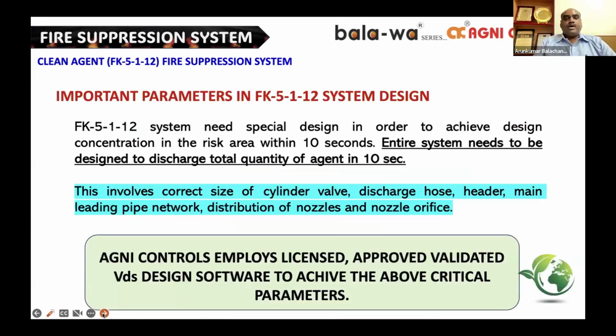The important parameter in an FK system design is that any chemical suppression system needs to achieve 85% design concentration within 10 seconds. So the entire discharge of an FK system, or the 85% design concentration of the FK system, has to be achieved in 9.9 seconds, which means we need to design the correct pipe size and the nozzle orifice size to have an effective and correct fire suppression. And Agni Control's Bala-wa 5-1-12 is again designed using a VDS German approved software.